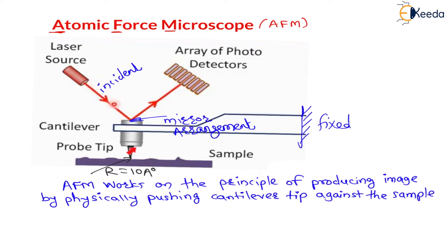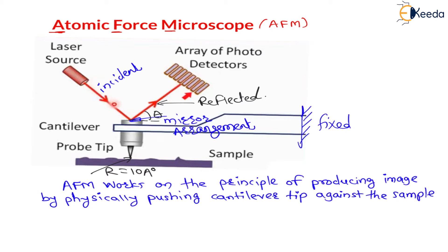Because of nano irregularities on the sample, this tip will move in the upward and downward direction. As this tip moves, this cantilever will also get motion in the upward and downward direction. Because of this, the incident angle on the mirror arrangement changes, so there will be reflected rays from this mirror arrangement. The laser light gets reflected, and because of this upward and downward motion, the angle of reflection, theta, gets changed. This reflected laser light gets collected with the help of an array of photo detectors, and this tip motion is analyzed.